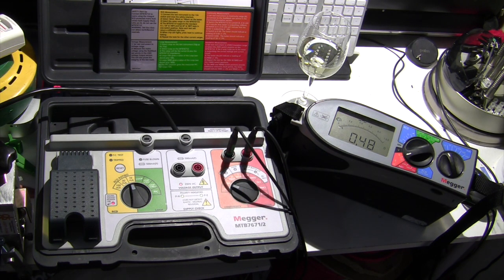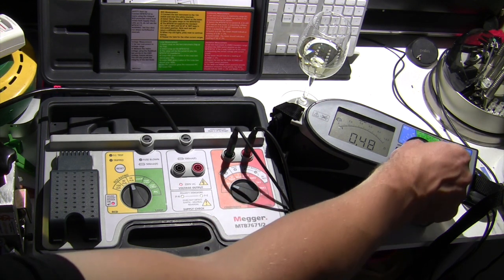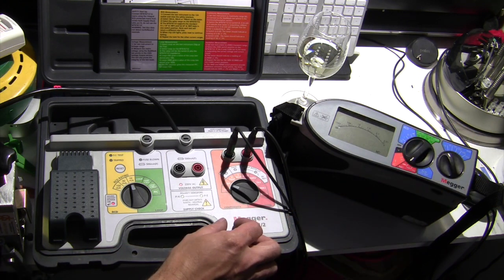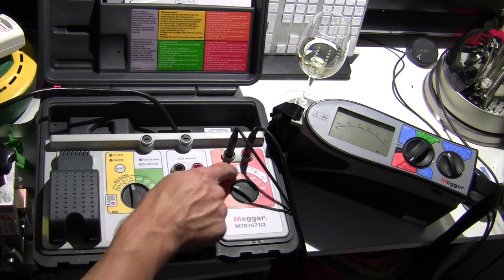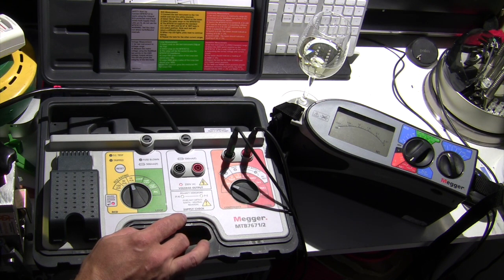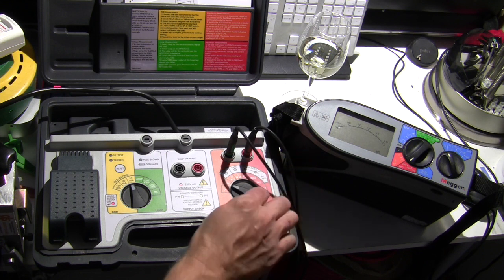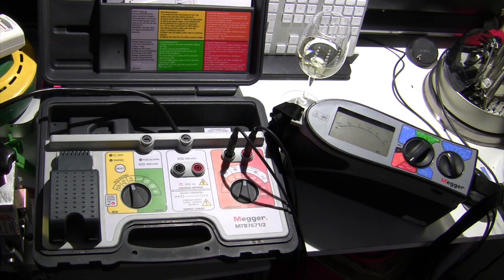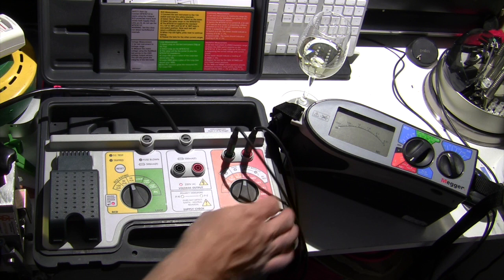Now I've just switched that to the 0.5 ohm range, and again we're getting somewhere close to that, 0.48. It's within tolerance, so we're all right on that one. And then we're going to switch now to the insulation resistance testing. There is this V-test and I-test thing here. You know what, I can't remember what they do now, I never use them, but if I remember rightly, one or both testers didn't like that test. I can't remember what the issue was now, it's about a year ago that I was playing with that. Anyway, we'll skip that and we'll go on to the 250 volts IR test.